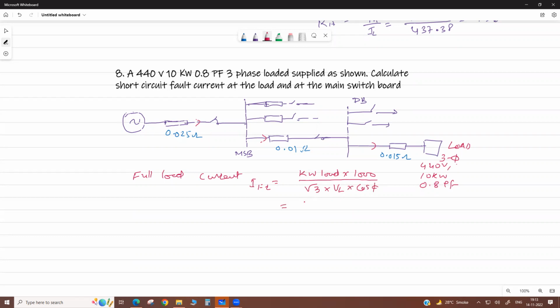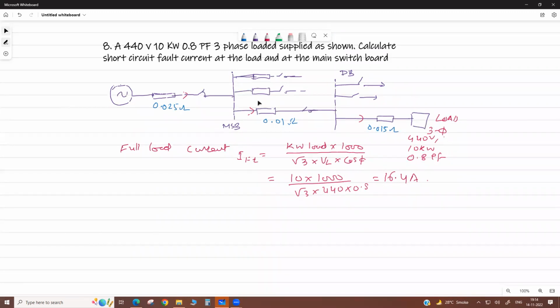Very simple. It is 10 kilowatt times 1000 divided by √3 times 440 times 0.8, which gives about 16.4 ampere only. Okay. But now suppose a short circuit occurs at the load end, point F1, or maybe they ask about a short circuit at the DB, distribution board. He is also asking about a short circuit at this MSB bus bar, point F2.